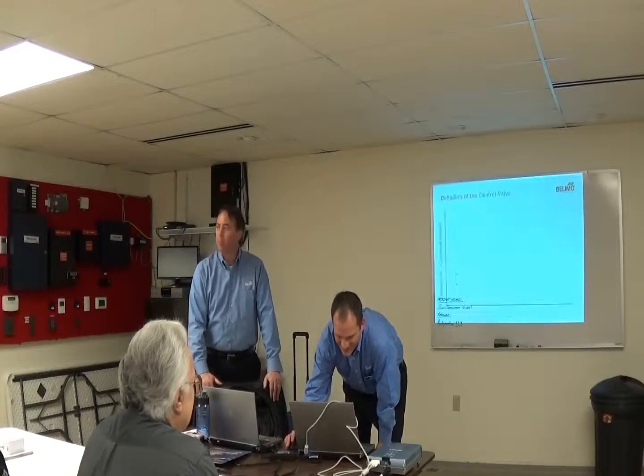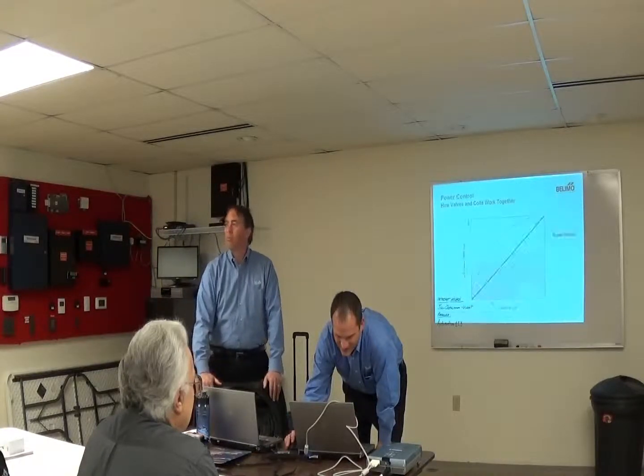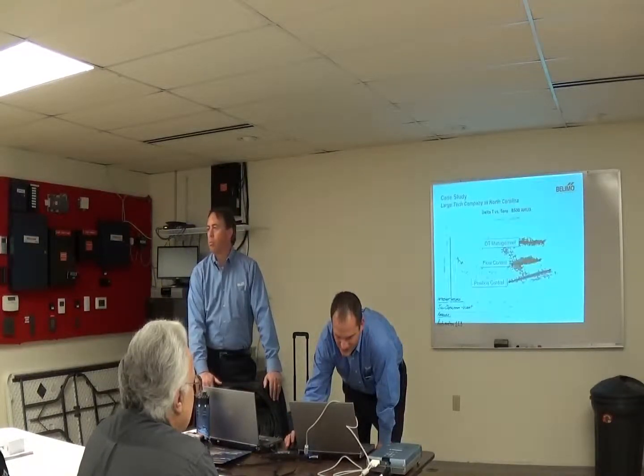If you can hook it up to BACnet IP, can you also still hit the web server? No, so you have to choose. Yeah, one or the other. Or you can do BACnet MSTP and the web server at the same time. But we've only got one Ethernet port, so you can only do one protocol, either our web server, WebQ we call it, or BACnet IP. Sorry.